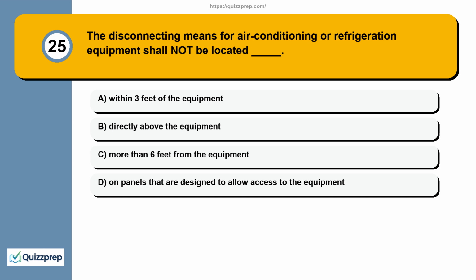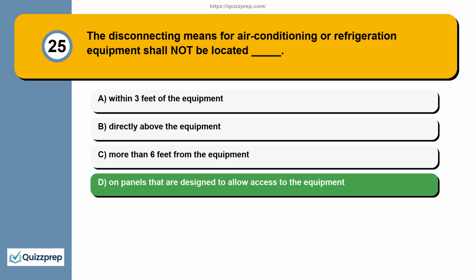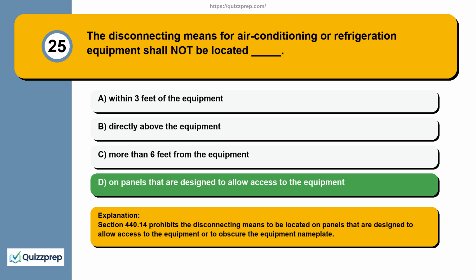Question 25. The disconnecting means for air conditioning or refrigeration equipment shall not be located within 3 feet of the equipment, directly above the equipment, more than 6 feet from the equipment, on panels that are designed to allow access to the equipment. Section 440.14 prohibits the disconnecting means to be located on panels that are designed to allow access to the equipment or to obscure the equipment nameplate.